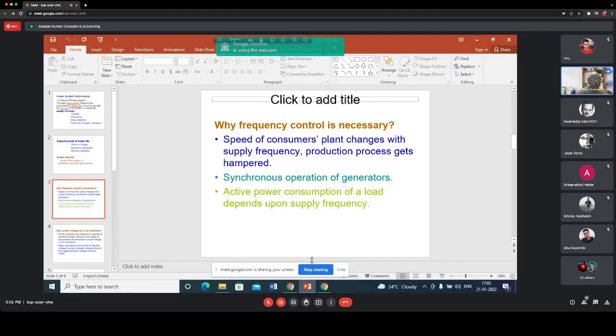Most of the generators in power systems till today are synchronous generators. In any power system, whether Indian or elsewhere, around 80% of the generators are synchronous generators. The remaining 20% of power comes from renewables, which have induction generators and solar PV. So excluding solar and wind, around 80% is from synchronous generators. If synchronous generators are to run in parallel, their frequency must be the same, and we can say that all the generators in a power system are effectively connected in parallel.